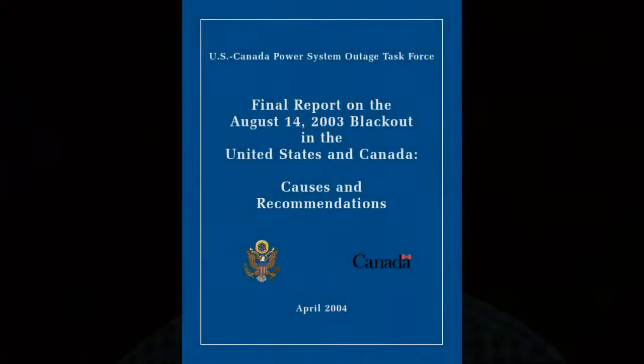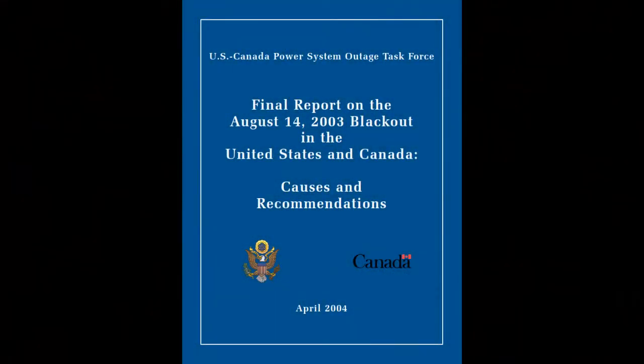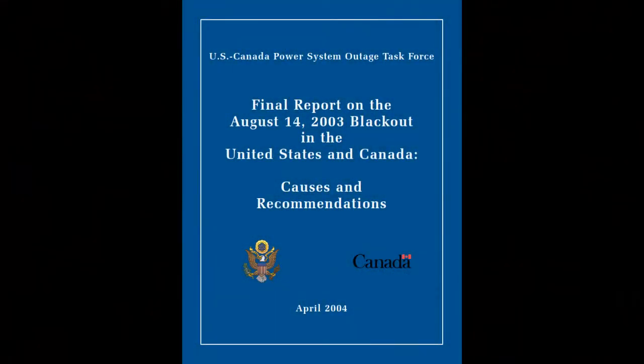Their research and findings are documented in a final report. And although there is not a single cause of the blackout — for a blackout to occur on such a massive scale, the causes are complex and multifaceted — a dominant source or cause of this blackout was inadequate reactive power injection. In other words, the starting point of the blackout, which exposed weaknesses in the grid's communication infrastructure, was inadequate reactive power injection.